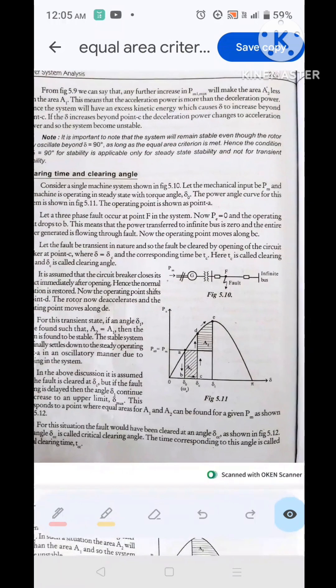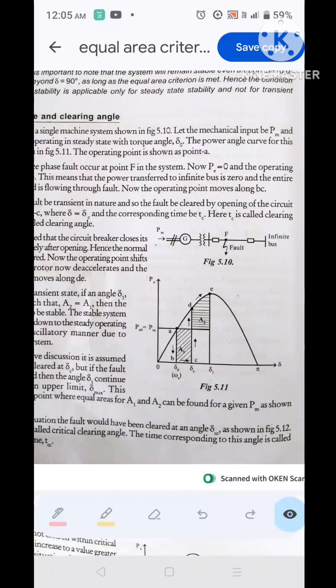Next is clearing time and clearing angle. A fault — say a three-phase fault — occurs somewhere between the generator and infinite bus. Since all electrical power transfer to the infinite bus is interrupted, the operating point immediately shifts from A to B. During the clearing time tc, the rotor angle changes from delta₀ to delta_c. The circuit breaker contacts then open.